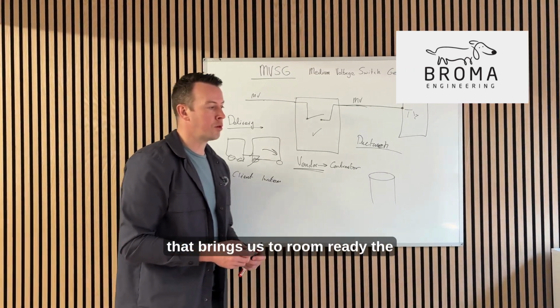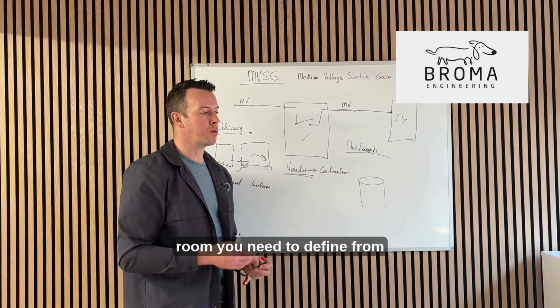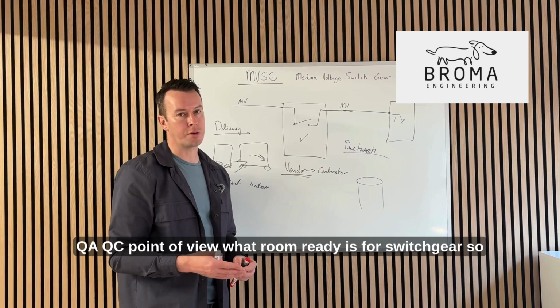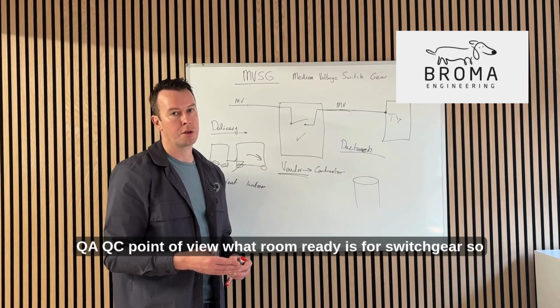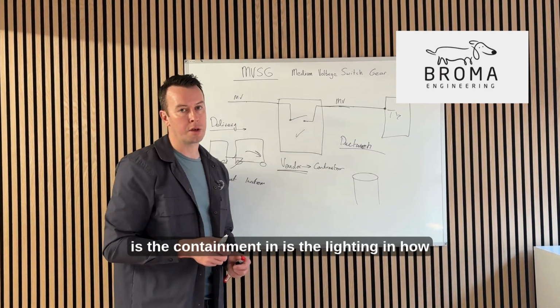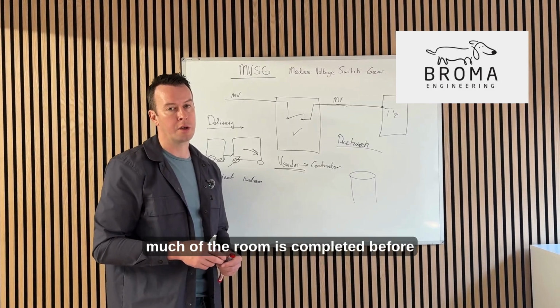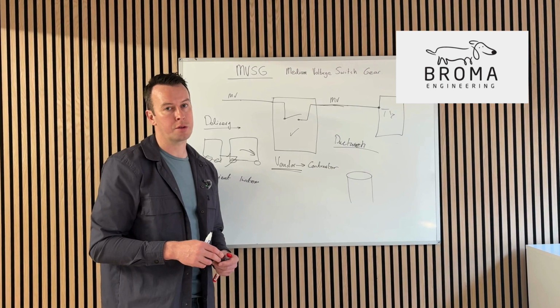And that brings us to room ready. You need to define from a QA/QC point of view what room ready is for switchgear. So is the containment in? Is the lighting in? How much of the room is completed before that switchgear gets rolled into place?